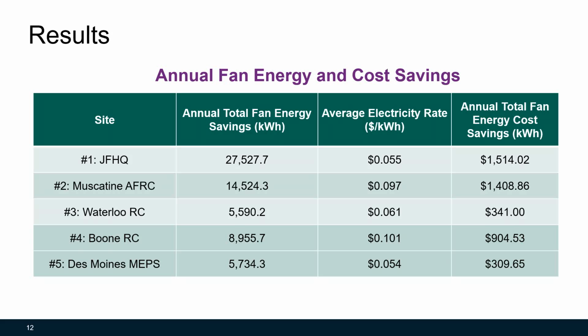For these 5 sites, the annual total fan energy savings ranged from 5,500 kilowatt hours to 27,500 kilowatt hours. The average electricity rates for these 5 sites range from 5 cents per kilowatt hour to 10 cents per kilowatt hour. And the annual total fan energy cost savings ranges from $300 to about $1,500.